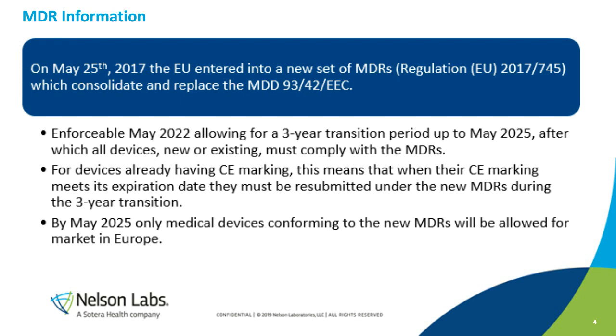1223-2009. On May 25th, 2017, the new Medical Device Regulation 2017-745 was published, which replaced the previous Medical Device Directive 93-42-EEC. These regulations are enforceable May 2022, allowing for a 3-year transition period of up to May 2025, after which all devices, new or existing, must comply with the new medical device regulations. Devices that already have CE marking will be good until the CE mark expiration date, and then documentation must be resubmitted under the new medical device regulations during this 3-year transition. By May 2025, only medical devices conforming to the new MDRs will be allowed for market in Europe.